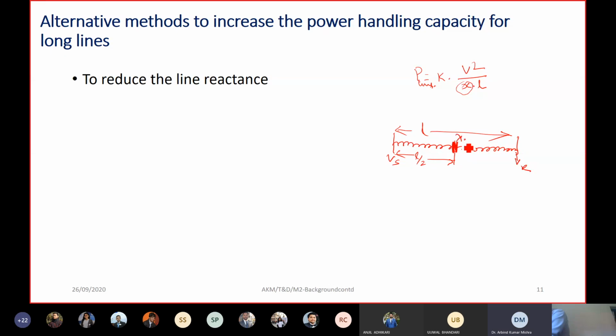Exactly at the middle, I have put a capacitor having a capacitive reactance of XC, in series with the line reactance. So the total reactance of the line becomes XL minus XC. Now suppose you make XC equal to XL by half, just one case, not always it should be half. If you put a series capacitor having capacitive reactance equal to half of the total line reactance, you can see that your power transfer limit can be made double.